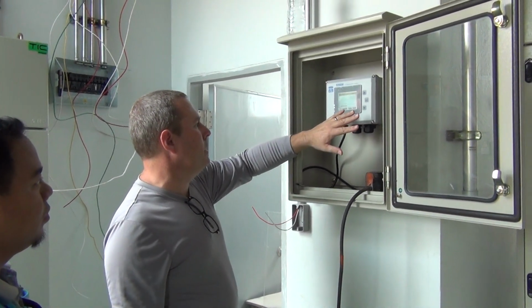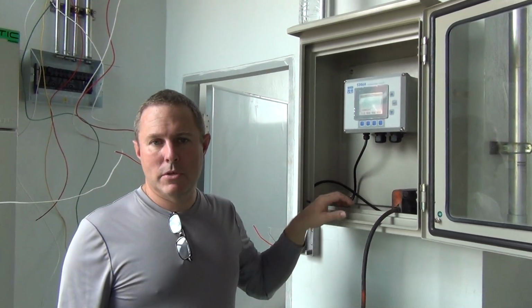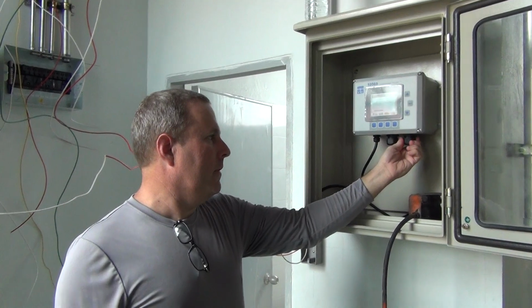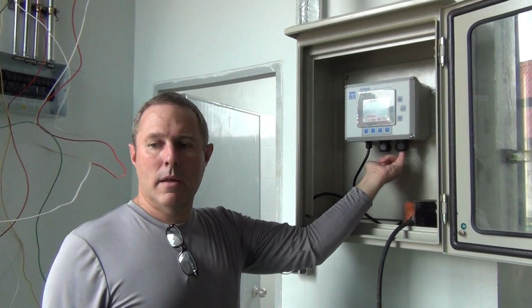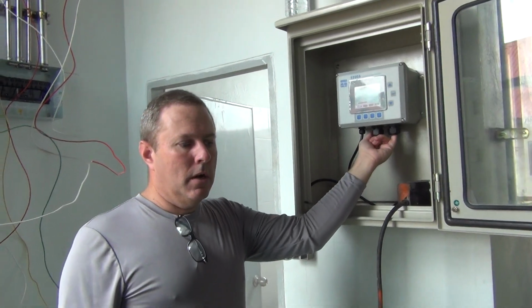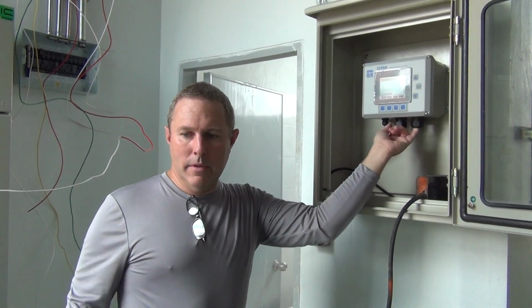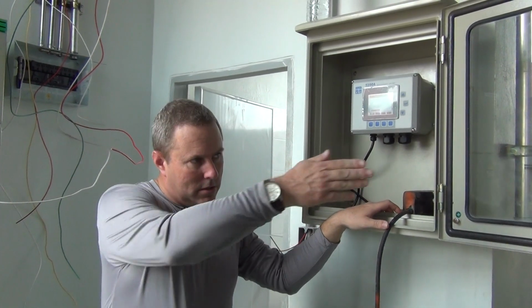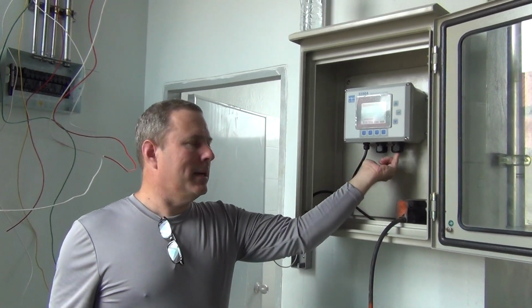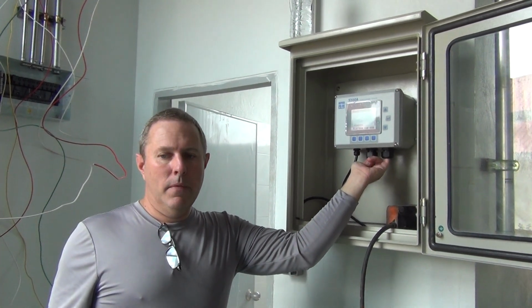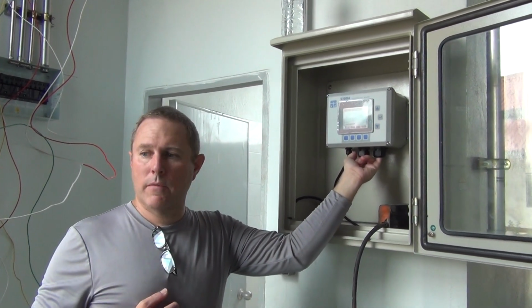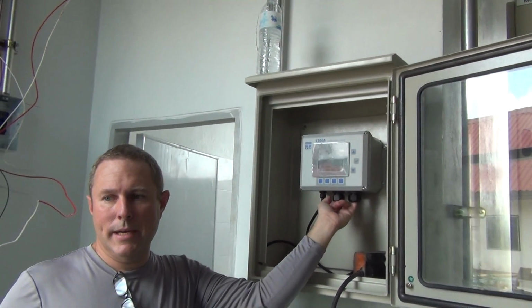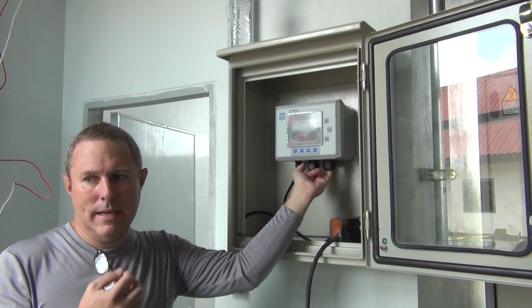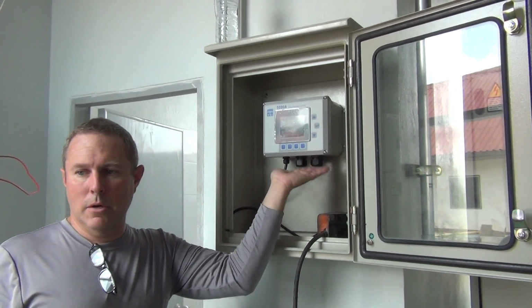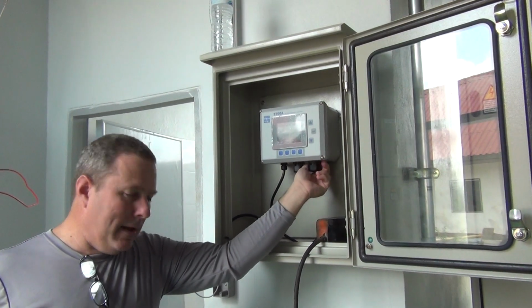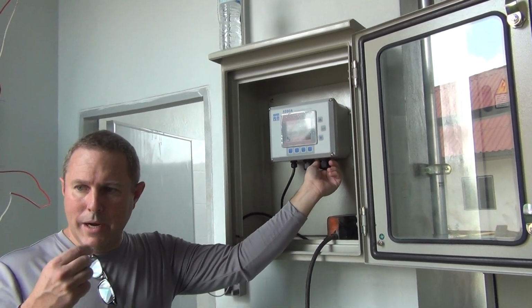So I think that's all that's going to be critical. The last piece is this connector right here has to be sealed. Whatever wires we're going to run in and out, the Ethernet, the communication wires to the PLC, the longer this is open and exposed, the more you will have corrosion and the board will damage over time. The manufacturer YSI would not warranty it if they see corrosion inside the unit, because that means you left this open. So I would recommend that today we close it until you're ready to run your wires through.